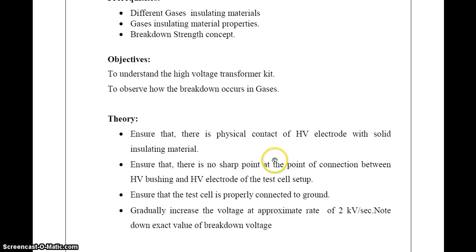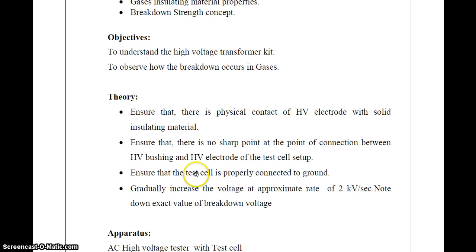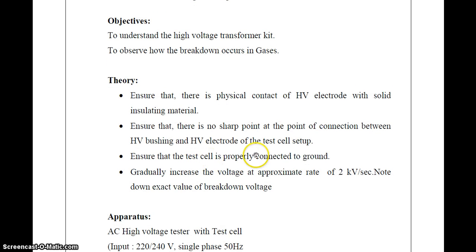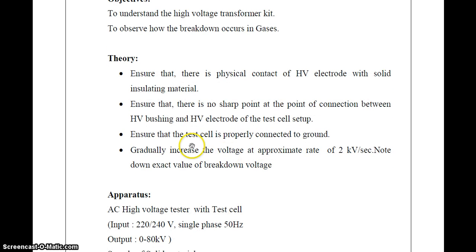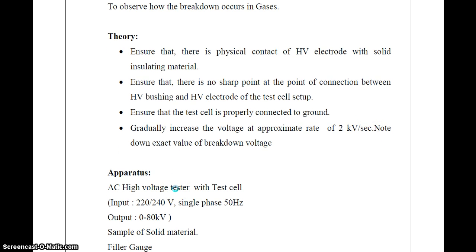Ensure that there is physical contact of the high voltage electrode with the solid insulating material in which we are using gaseous insulating material. Then ensure that there is no sharp point at the connection between the high voltage bushing and the high voltage electrode of the test cell setup. Then ensure that the test cell, that is the sphere cell, is properly connected to the ground. Gradually increase the voltage at an appropriate rate of 2 kilovolt per second. Note down the exact value of breakdown voltage.